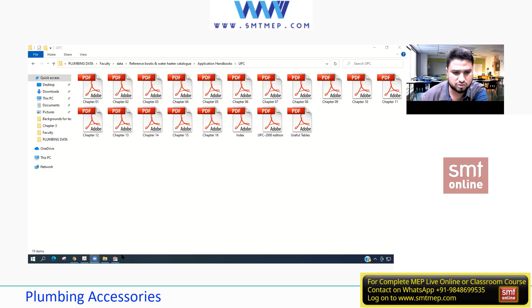So as of now, just to remember: to find out the pressure exerted over here, we have a formula. Pressure exerted at the bottom of one liquid column of height, P equals H into 0.433 PSI, where P is the pressure we are trying to find, and H is the height in terms of feet, and 0.433 PSI is the standard constant, with units in PSI.